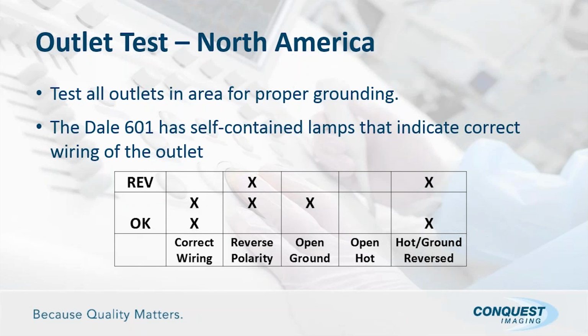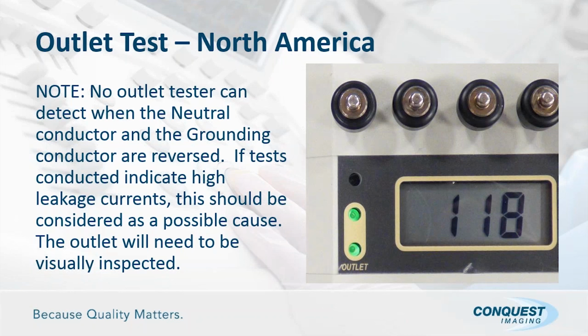But the reason I bring it up is if they're reversed, you can get some very unusual electrical safety readings, and it may exceed the limits. And if you've checked everything in the system and you still haven't come up with a solution, then this is a time to go back to your wall outlet and have your facilities people look at the outlet and make sure that it is indeed correctly wired. And here's the lights I was referring to, and here is the actual note that says that you can't test an incorrect wiring between neutral and ground if they're reversed.